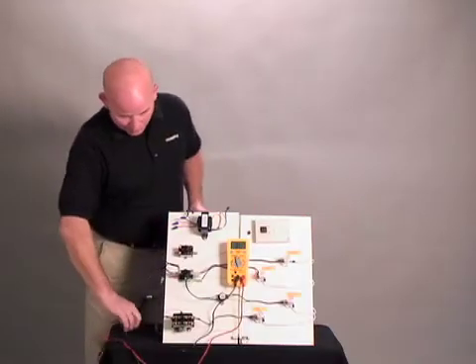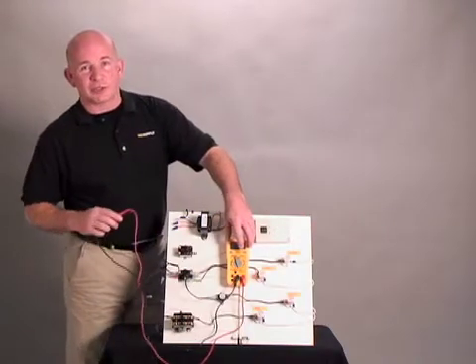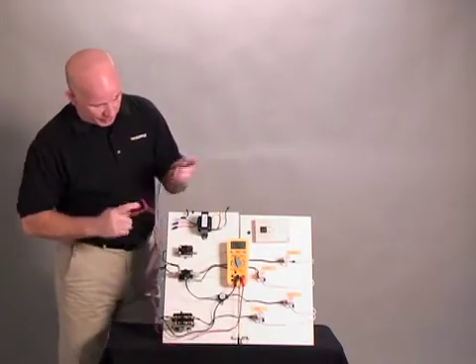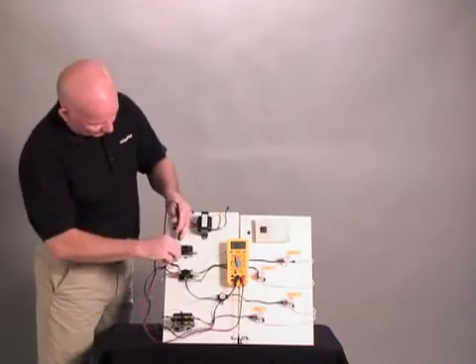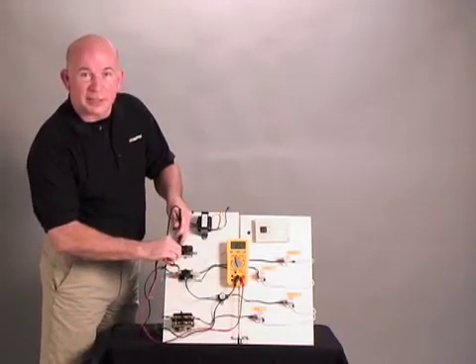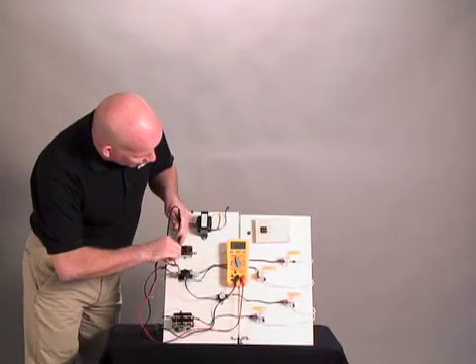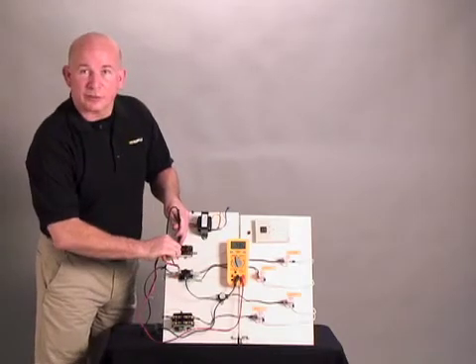To test the fan relay, set your meter to the lowest resistance level and you should read approximately 70 to 80 ohms of resistance. We're showing 79. It's good.